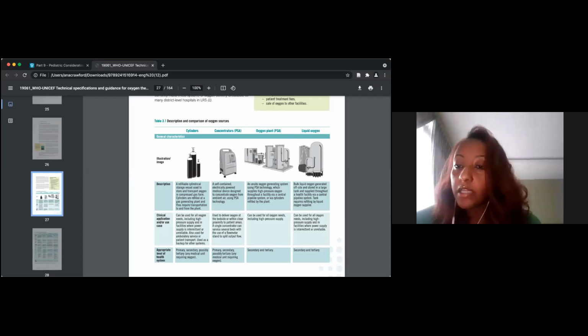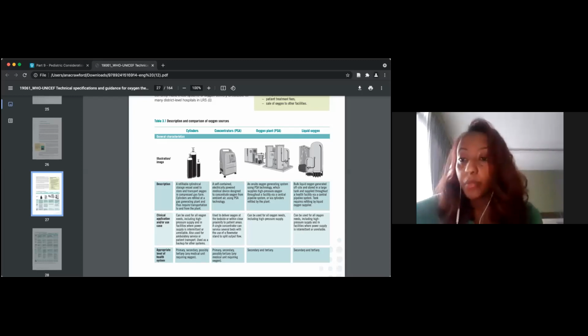When it comes to clinical application, most of these can be applied in different settings. Cylinders can be applied to different levels of healthcare facility. They can be used for all oxygen needs, including high pressure supply, and in facilities where power supply is intermittent or unreliable because they do not require electric sources. Concentrators can be used to deliver oxygen at the bedside or within close proximity to patient areas, and a single concentrator can service several beds with different flow meters and divide among patients.